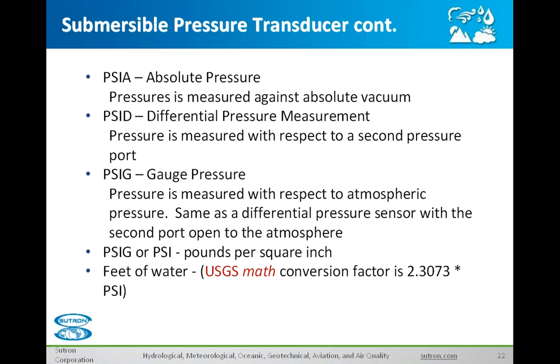There are a number of different types of pressure transducers. There's the absolute type — this measures pressure up against it, and if it's submerged in water, it measures the weight of the water. But it is also measuring the barometric pressure as well — the weight of the air does affect that. So to get actual water level readings, you have to have a barometer at the surface and subtract off the barometric pressure for each reading.